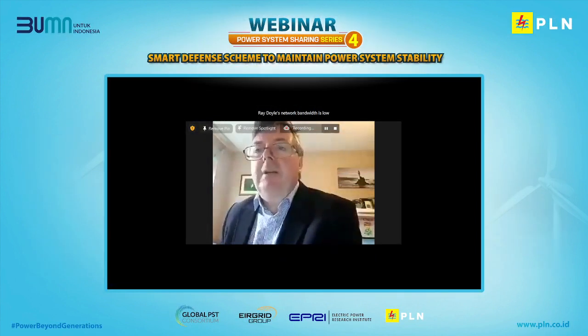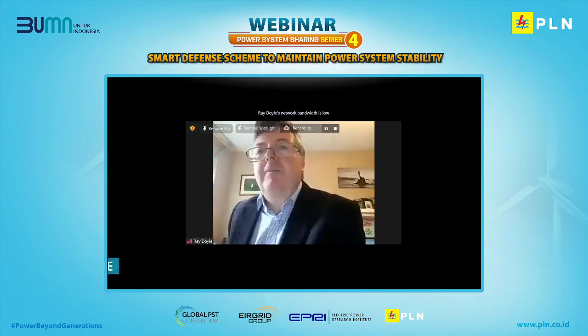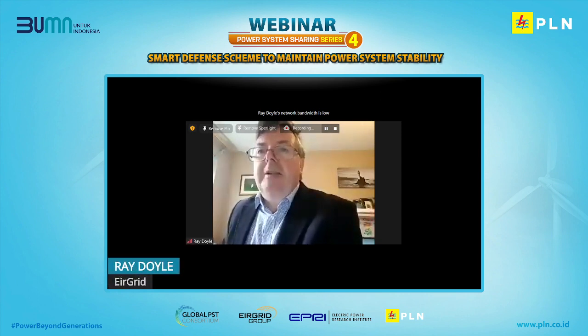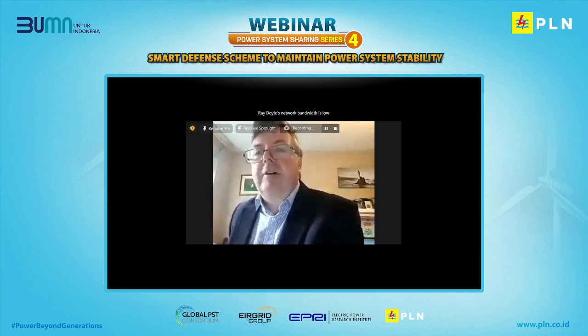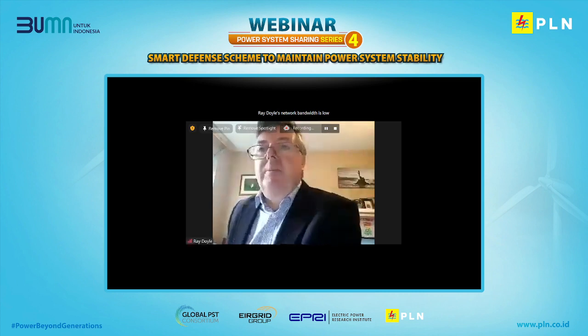Okay, so the first question, on the inertia. We have changed our system to allow rocof of up to 1 hertz per second. All the rocof settings have been increased up to 1 hertz per second on distribution connected generation. We don't employ rocof protection on the transmission system, but all the rocof relays have been set up to 1 hertz per second on distribution connected generation. Also, in the control center, we keep track of the conventional plant that's on the system, so we keep track of their inertias. We operate a minimum amount of inertia, so we always make sure there's sufficient inertia on the system to maintain rocof within 1 hertz per second. That sometimes requires us to constrain on conventional plant that maybe wouldn't otherwise be needed.